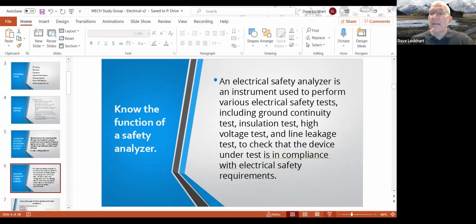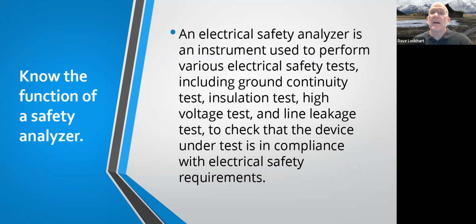All right, electrical analyzer. An electrical safety analyzer is an instrument used to perform various electrical safety tests, including ground continuity tests, insulation tests, high voltage tests, and line leakage tests, to check that the device under test is in compliance with electrical safety. So a lot of facilities have these, use those for any electrical equipment that gets introduced into the facility. You want to make sure that it is properly wired, doesn't have any leakage to ground. You want to make sure it's got a ground post.